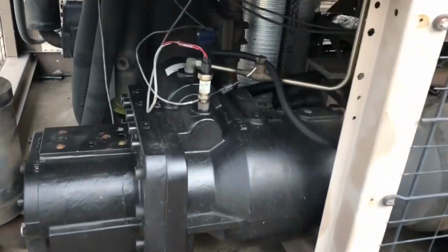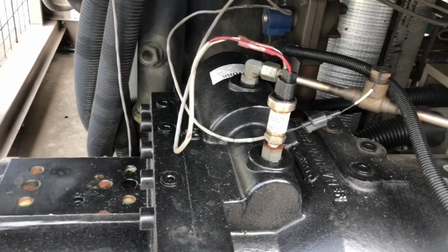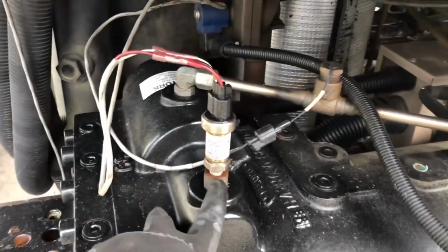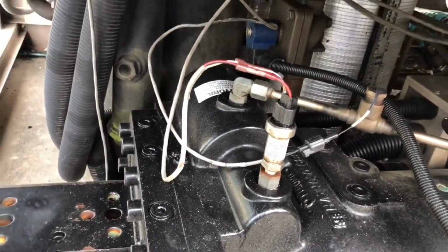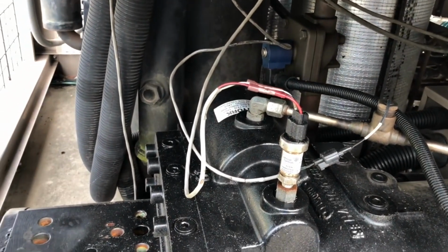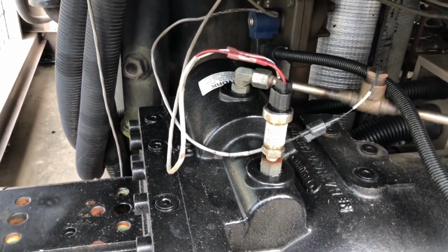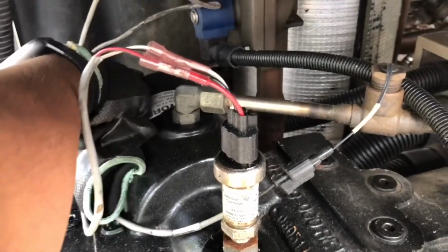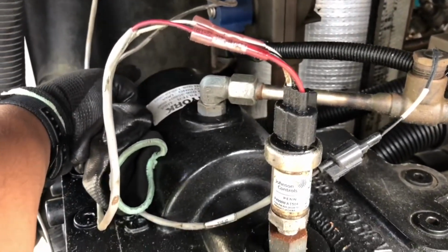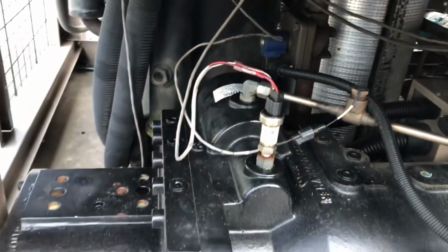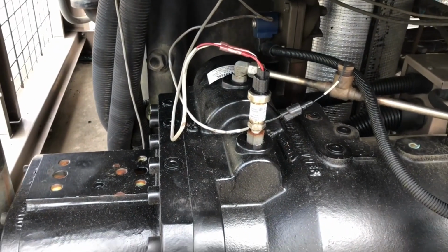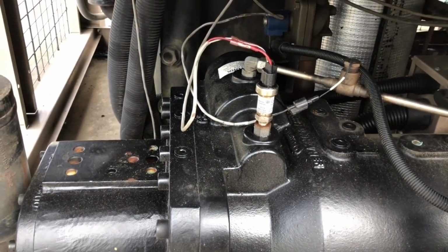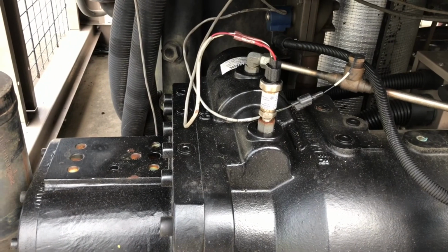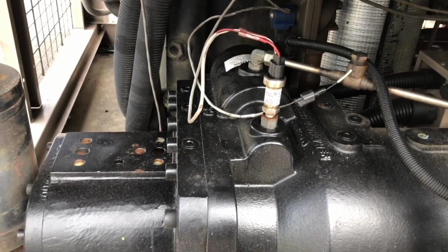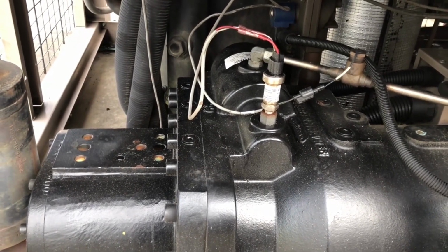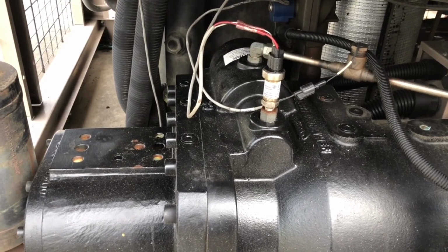So what are we gonna be doing? We're gonna be taking this oil pressure transducer off because it's giving me bad readings. We'll start by putting a pressure gauge in the back, so we can measure the pressure there since there's no Schrader valve. Then we need to take the refrigerant and pressure out of that compressor so we can freely take the oil transducer off.